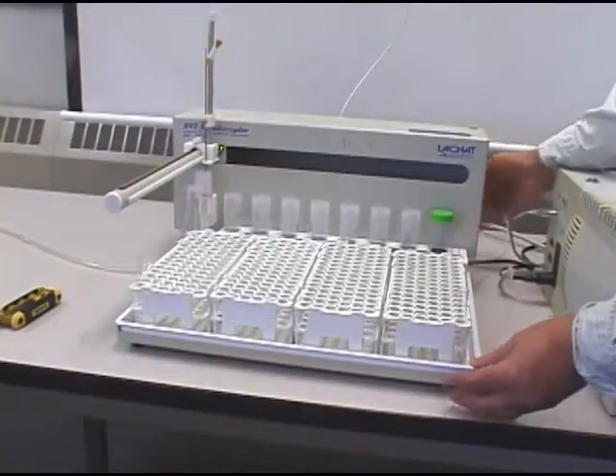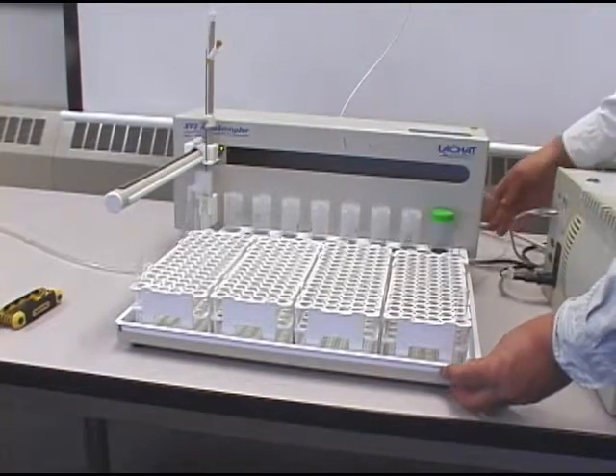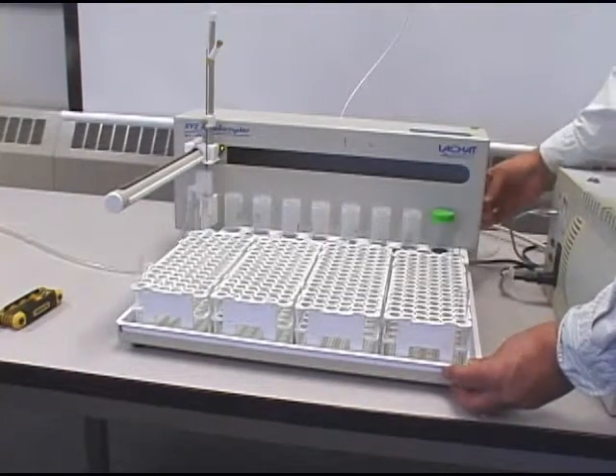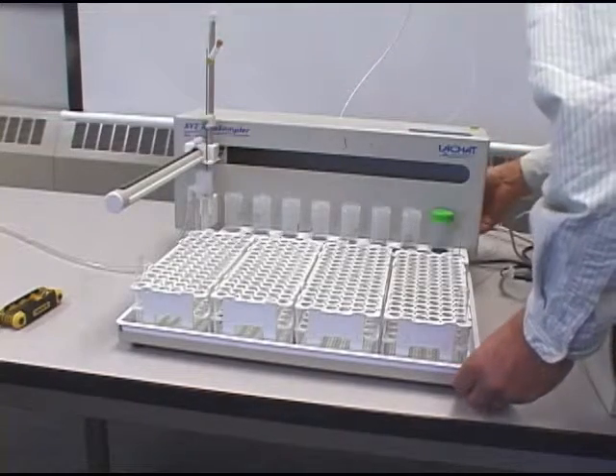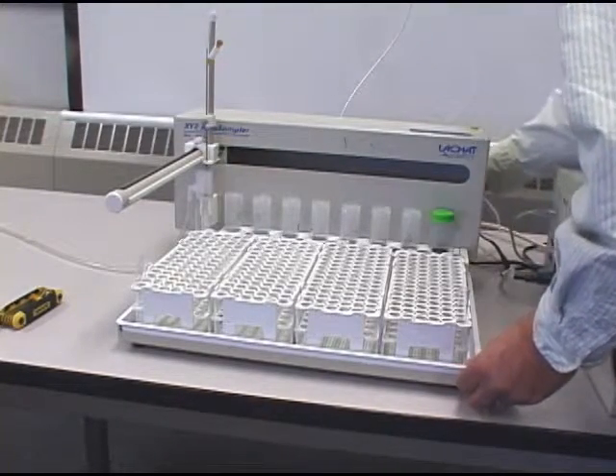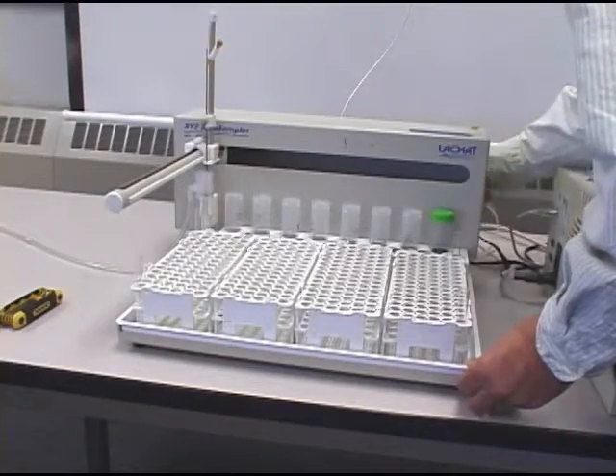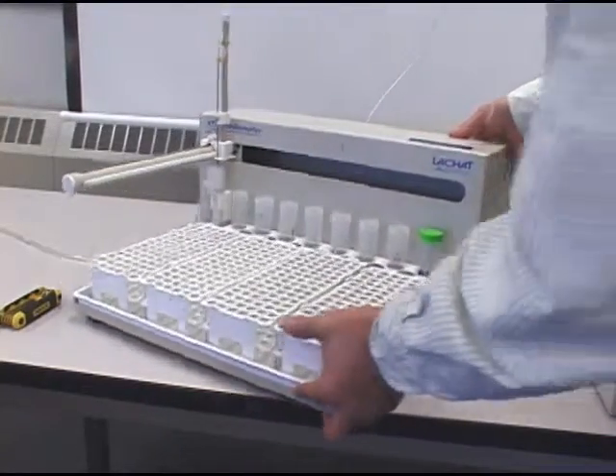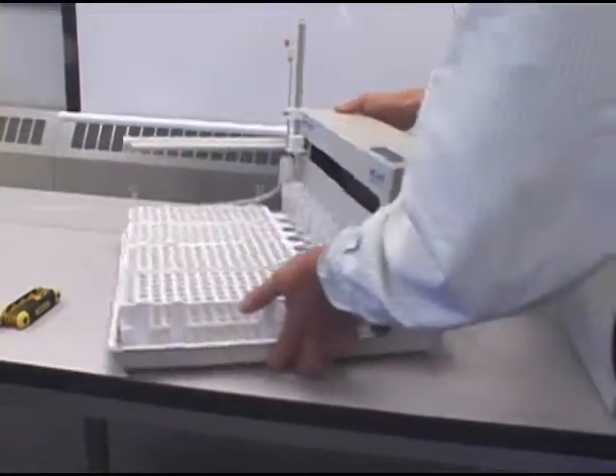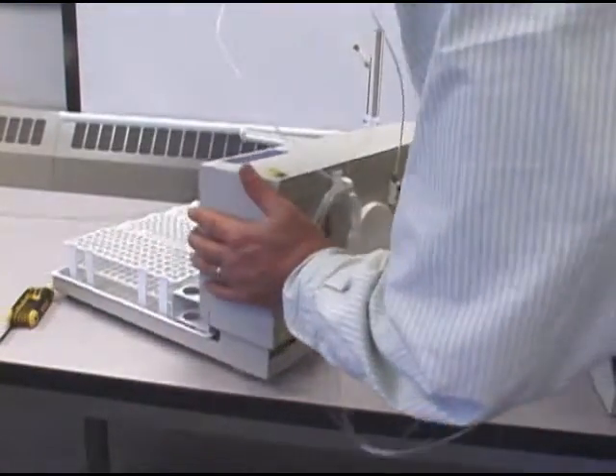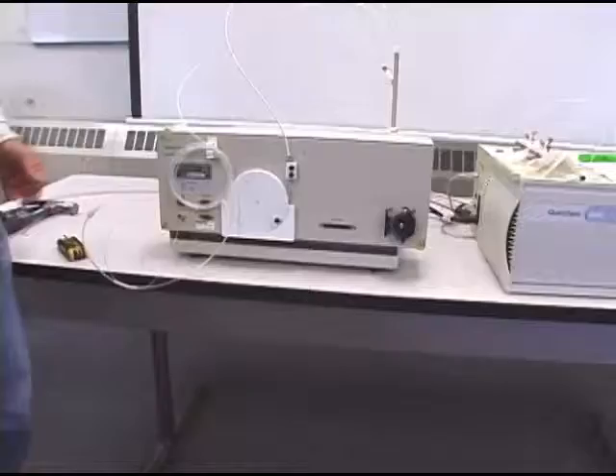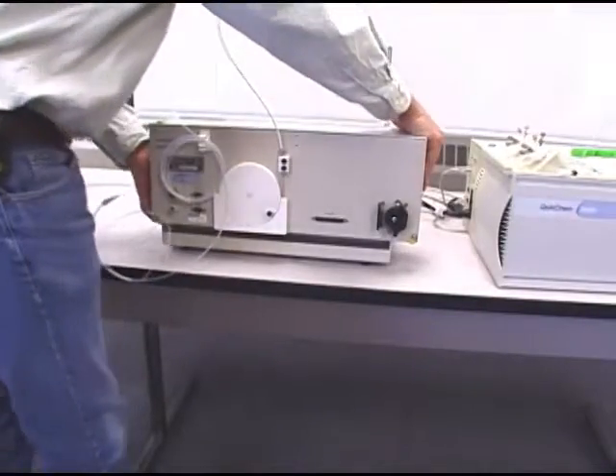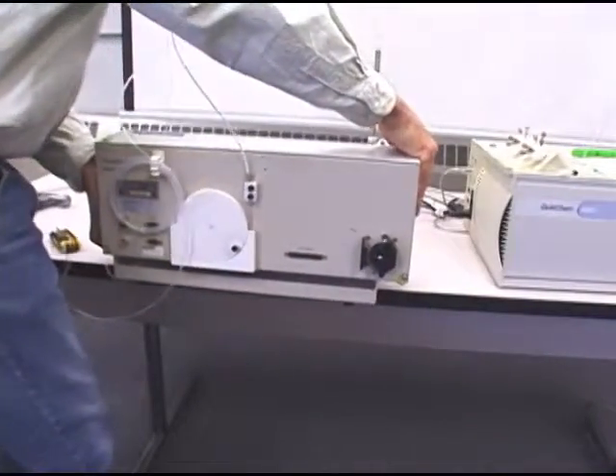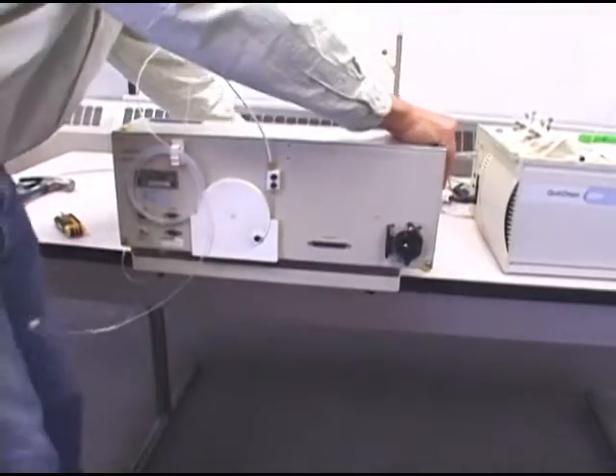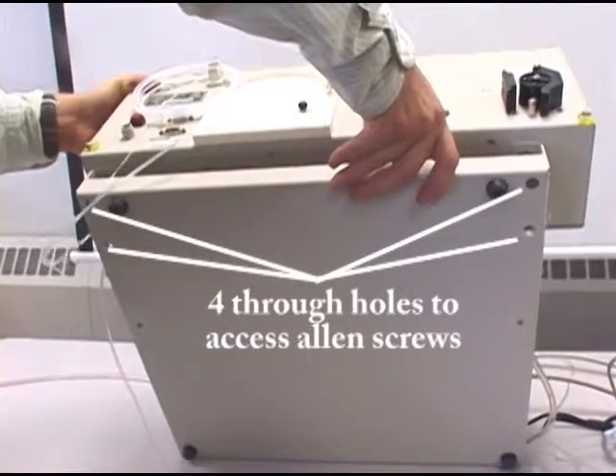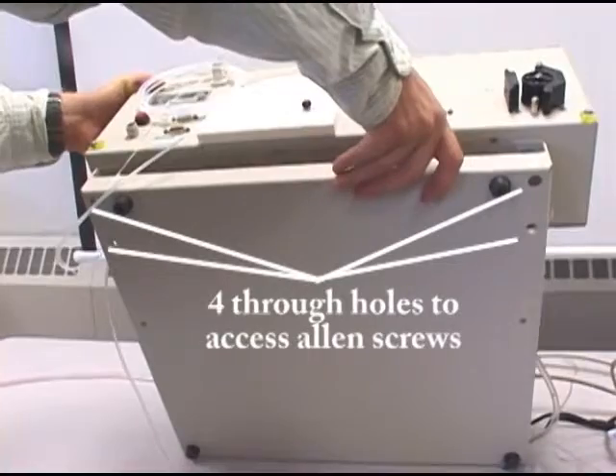Okay, now we're going to go ahead and adjust the tray with relation to the core here of the autosampler. So I'll turn the autosampler off, and what I'm going to do is disconnect the connections on the back, and I'll need to turn the autosampler such that I can get to the rear of it to make adjustments on the sample tray. So now that I've got the autosampler turned around, I need to pull it to the edge of a table so that I can gain access to the 4 screws that hold the tray to the main core.